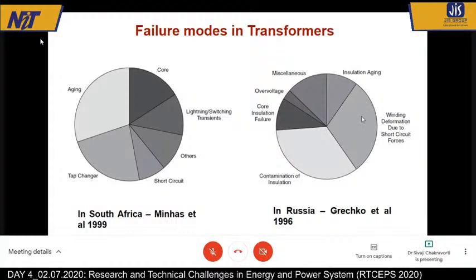On the right-hand side is another study done in Russia, where a large chunk is written as contamination of insulation. By the way, this contamination is not necessarily external contamination, it could be the result of aging. Here again you can see insulation aging stated separately. So if we take these two together, it is almost 50%. So it is quite obvious, and there is also core insulation failure. It is quite obvious that insulation is the primary weakest link in the failure of the transformer.